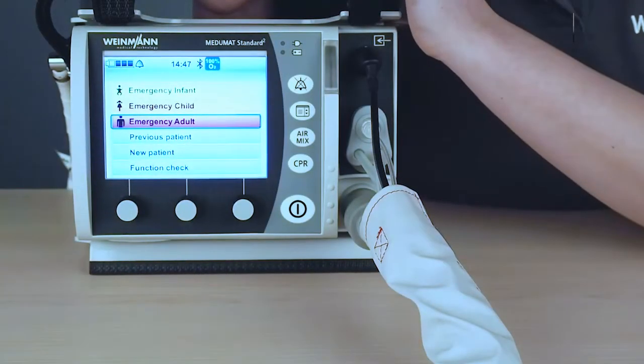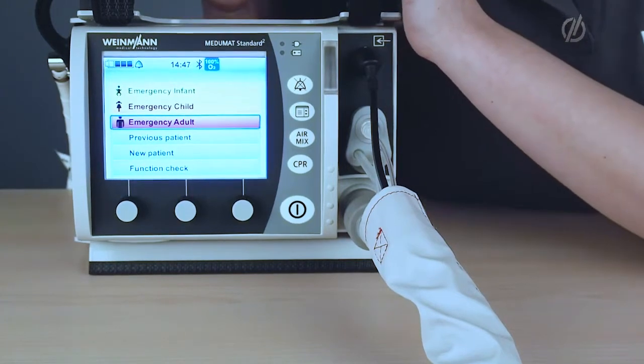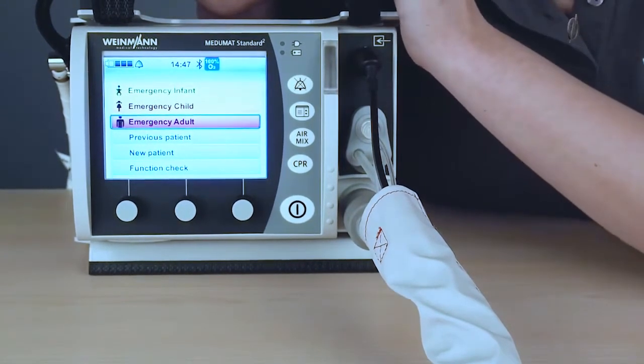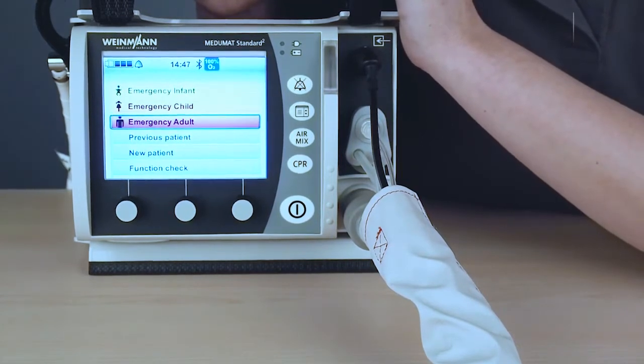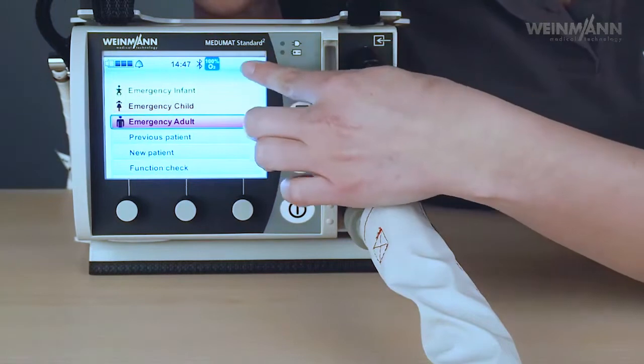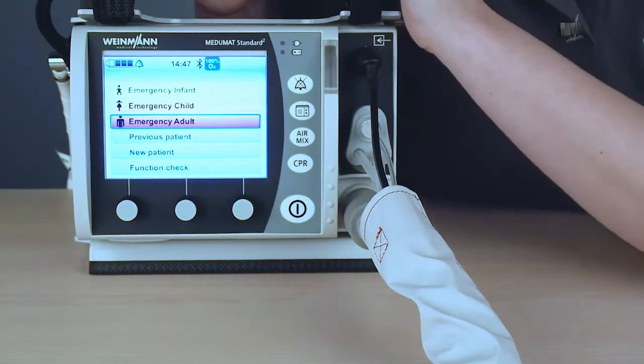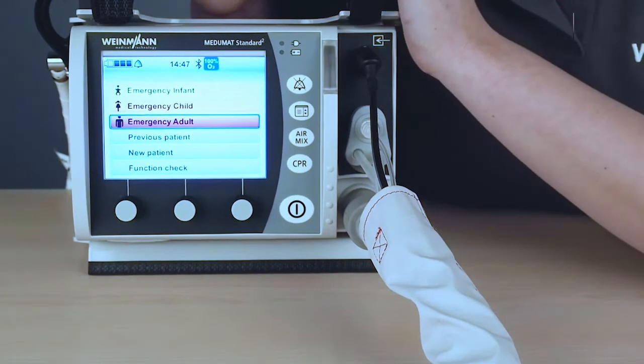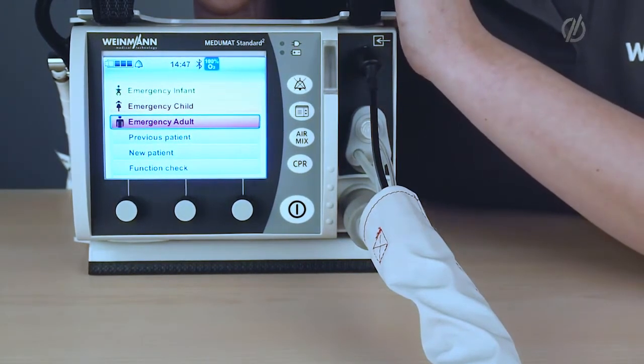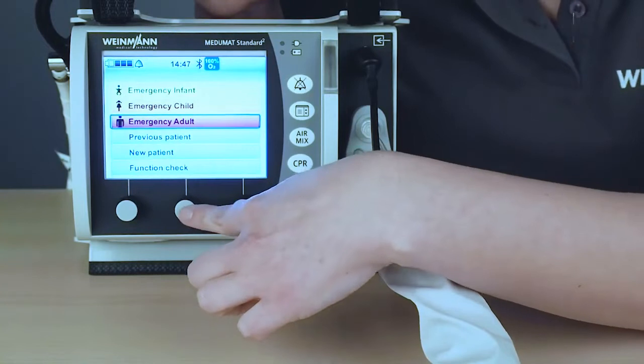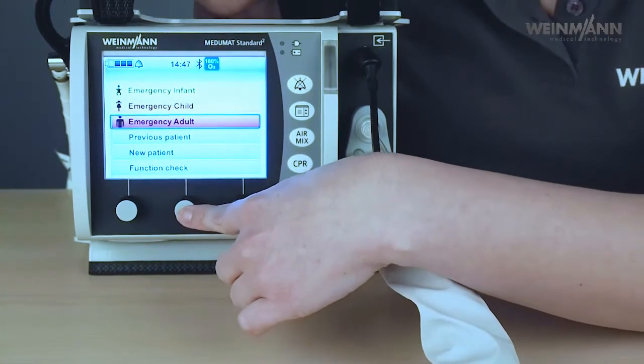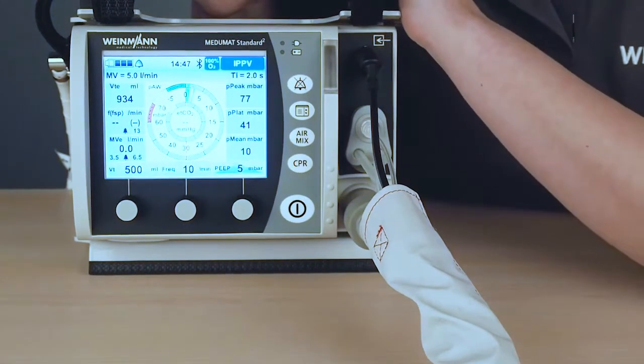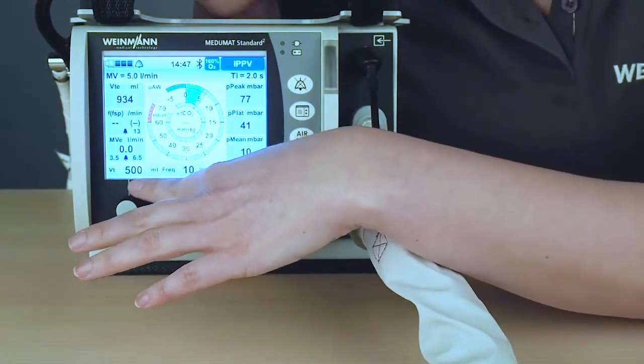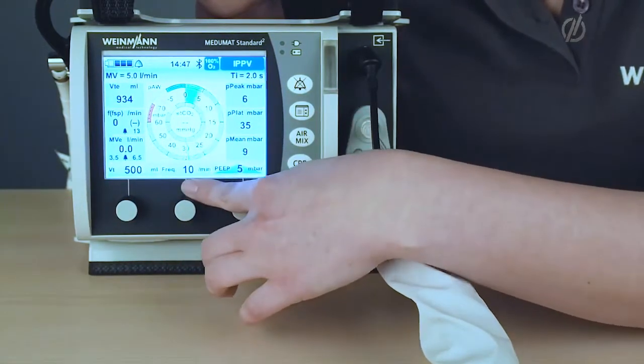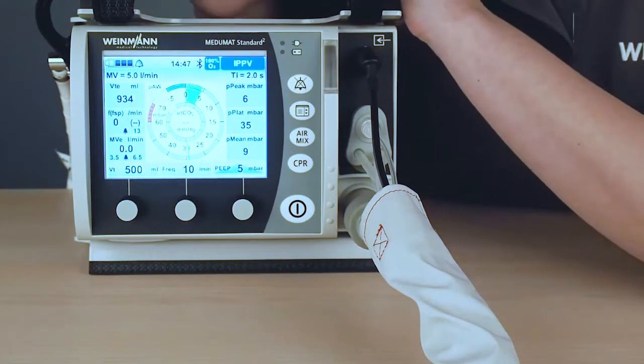So now I would like to show you how to work with the device and how to start a ventilation. For starting ventilation, you have different options. The easiest option is via the emergency modes. So here you have 3 different emergency modes for infants, childs and adults. And these modes are preset, so they are pre-configured settings. And with only one click on one of those buttons, you can start an emergency ventilation. In this case, a volume-controlled IPPV ventilation. You see here the settings for the adults are 500 milliliters in tidal volume and a ventilation frequency of 10. So very easy, very quick.